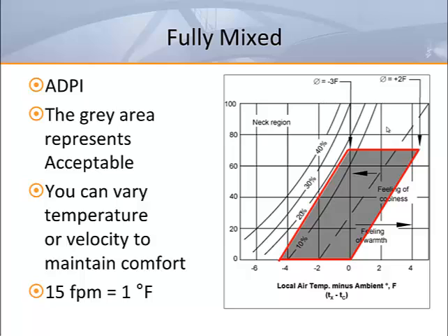The dashed line through the center of the parallelogram also shows a relationship between temperature and velocity of about 15 feet per minute per degree Fahrenheit. So each 1 degree rise in ambient temperature can be offset by adding 15 feet per minute to the room air motion.